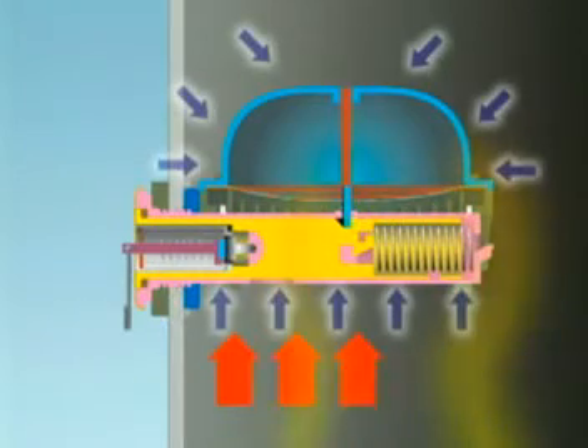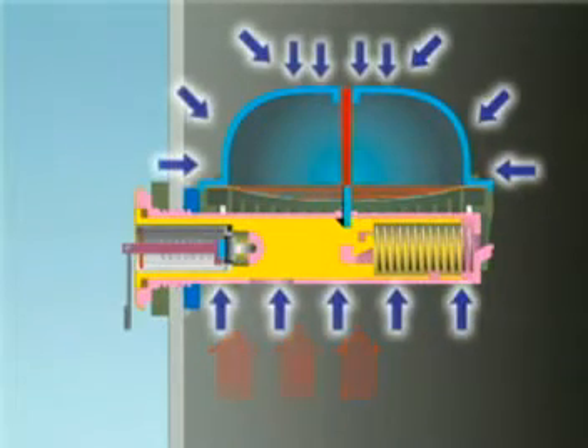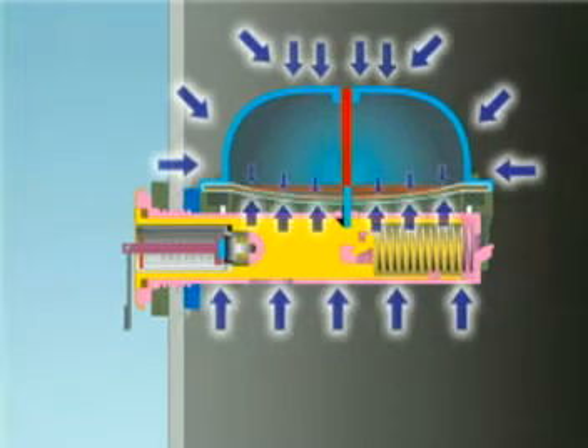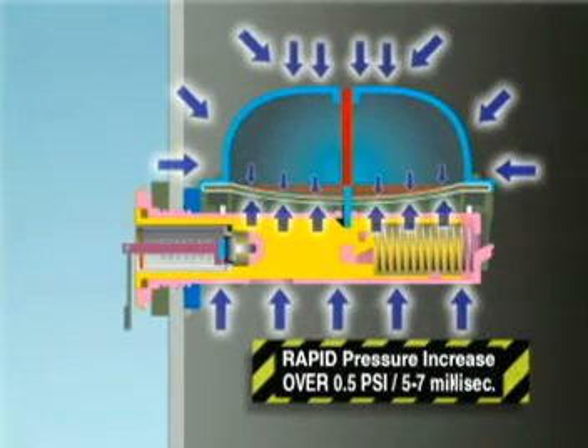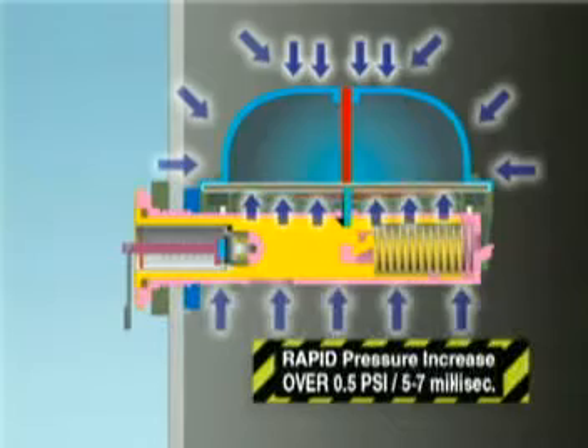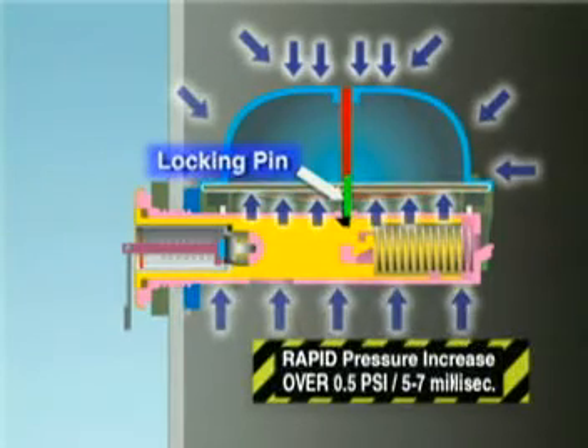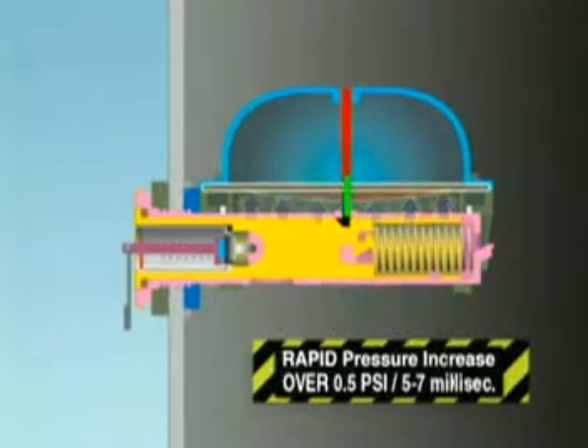After a fault, there is a sudden increase in tank pressure. The metered hole will not allow equalization of pressure on each side of the diaphragm if the pressure increases suddenly. The rapid difference in pressure causes the diaphragm to move up, releasing the locking pin, which triggers the highly visible indicator flag to pop out of the side of the transformer.